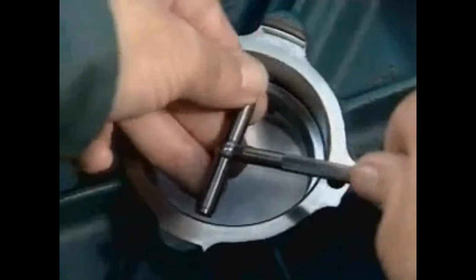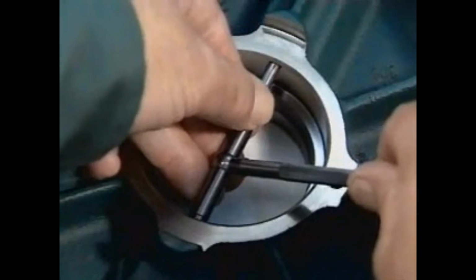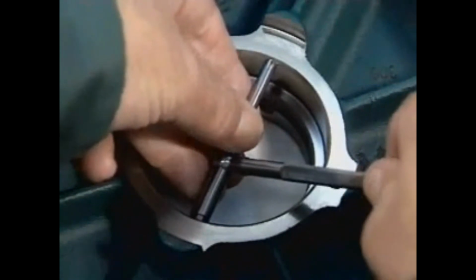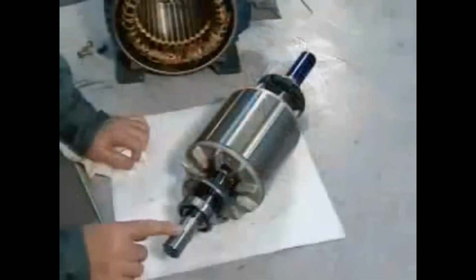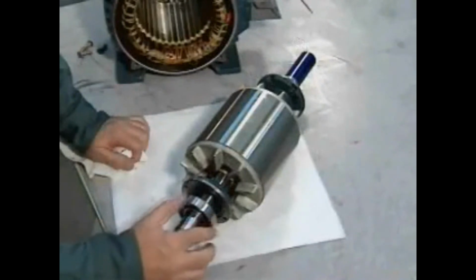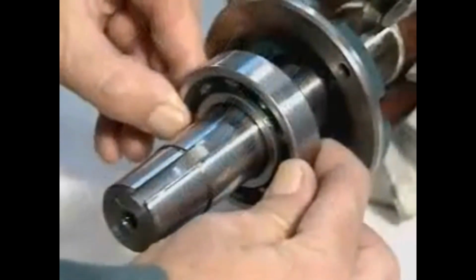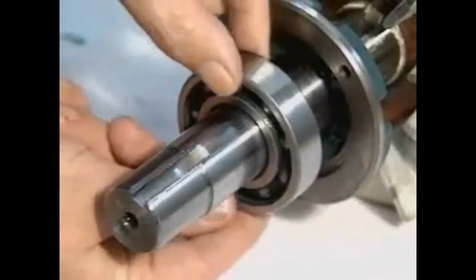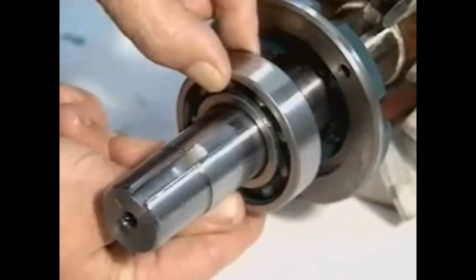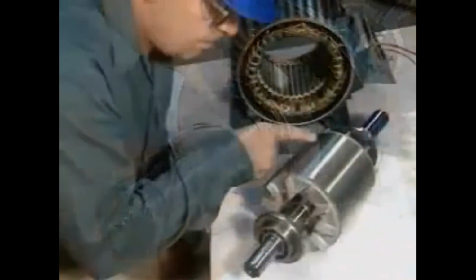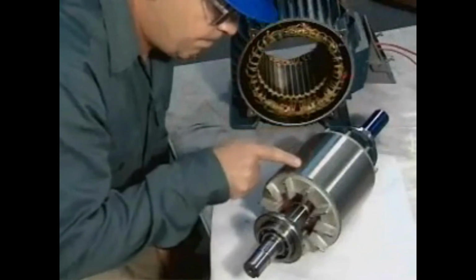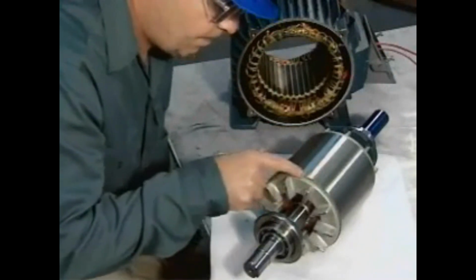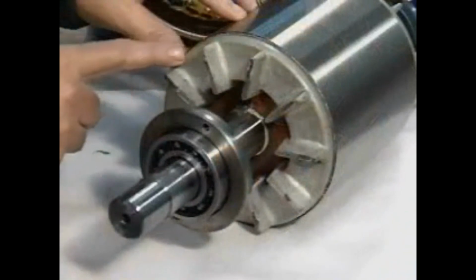Check the bearing seating surfaces of the end bells to determine if they are out of round, tapered, or worn. Inspect the shaft and bearings for signs of damage. If the bearings are bad, they will need to be replaced. Inspect the rotor for loose or broken bars, end ring damage, and overheating. Inspect the rotor fins for signs of damage.